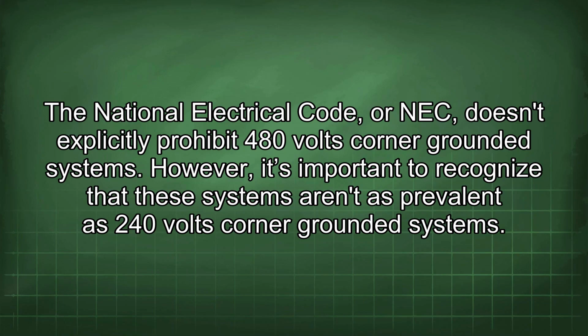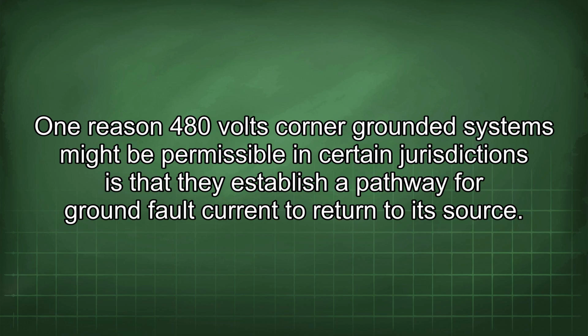The National Electrical Code, or NEC, doesn't explicitly prohibit 480 volts corner-grounded systems. However, it's important to recognize that these systems aren't as prevalent as 240 volts corner-grounded systems. One reason 480 volts corner-grounded systems might be permissible in certain jurisdictions is that they establish a pathway for ground fault current to return to its source.